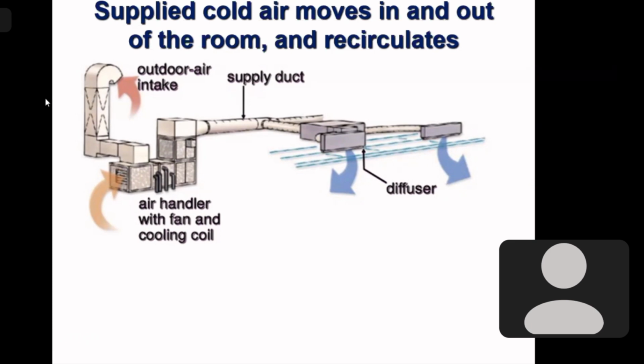So in the air handling unit, we take the return air from the room and mix some outdoor air with it. Why outdoor air? Because the room will have occupants. They need some oxygen for breathing. Now, if we don't give outside air continuously, after some time there will be a shortage of oxygen and the people will start feeling uncomfortable.